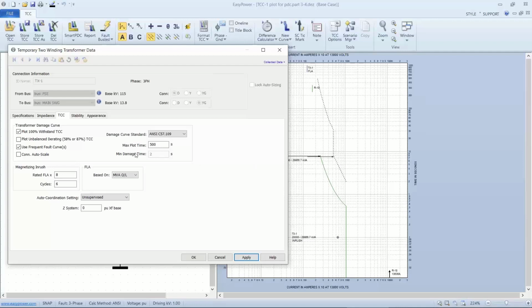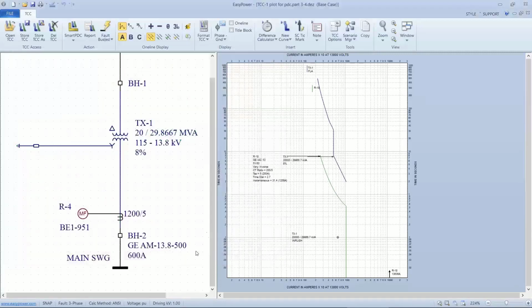Now, the thing that puzzles me is normally we see two plots on a transformer plot, and that's because for a single line to ground fault on a delta-wye transformer, we plot a derating curve, and it's a solid curve offset by 58%. But if you'll notice, this overwrote that curve that we had. So the question is, why don't we have a separated curve? Why don't we have two curves?